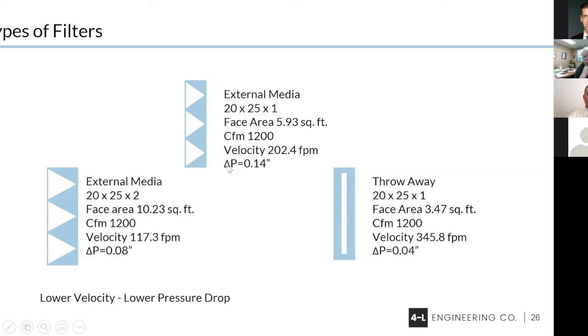By converting from a 1-inch filter to a 2-inch filter, down in my lower left, my face area now increases to 10.23 square feet, and my pressure drop goes down to around 0.08. So there are some things we can do for some units by simply changing the filter rack, putting in a wider filter. We can overcome some of the resistance problems that we're faced with. Next slide.